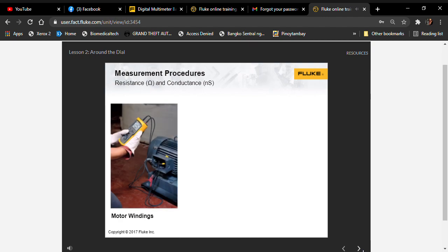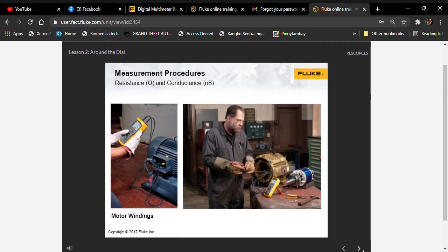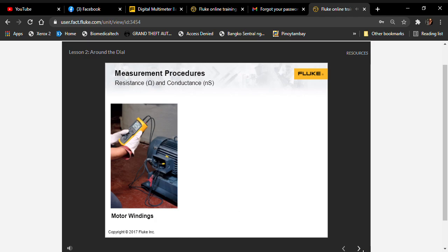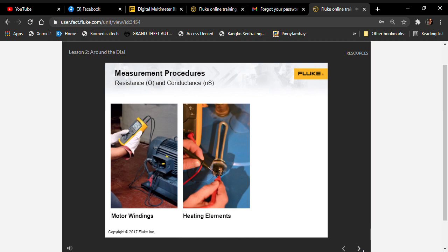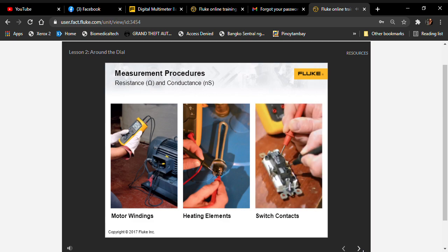Resistance and conductance are used for several types of tests. They're used to measure very high resistances in insulation meant to prevent current flow, like the insulation on motor windings. Periodic resistance testing can show if insulation is breaking down, indicated by falling resistance over time. Resistance measurements are also taken on components meant to have some resistance, like resistive heating elements, to check their condition. Finally, resistance measurements are taken on components intended to have very low resistance, like switch contacts and conductor connections and splices, to find spots that cause voltage drops and excessive heat.